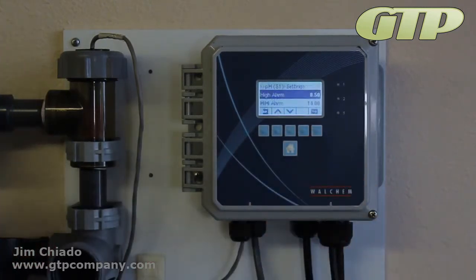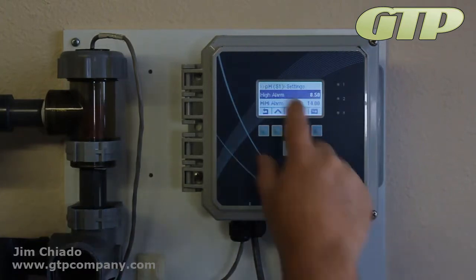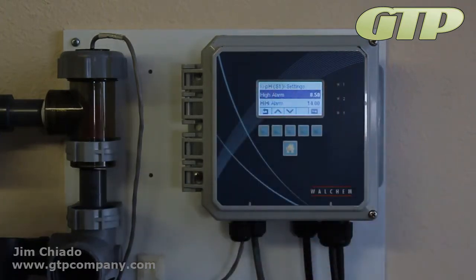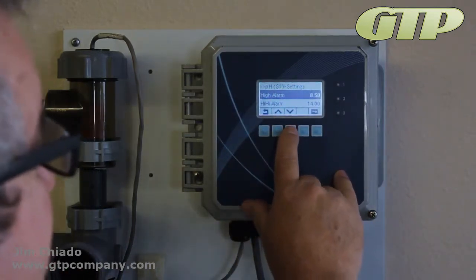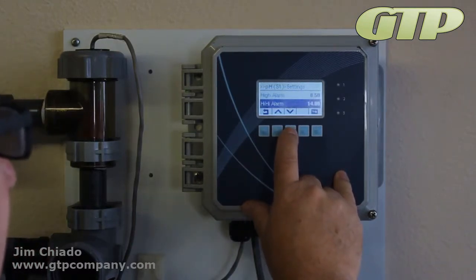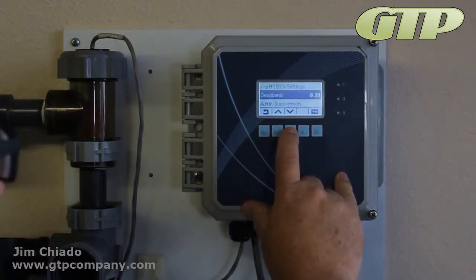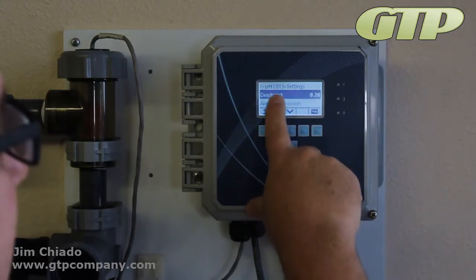Okay, and I do recommend setting those things. The more information you give your client before they come walking up that it's in alarm, or they walk by and maybe that's just their checkoff, the guy says, and he does see alarm at the top. At least maybe they'll stop. You know, at least the machine's trying to tell them something. High alarm, low alarm, I wouldn't necessarily set up, but you can if you want.